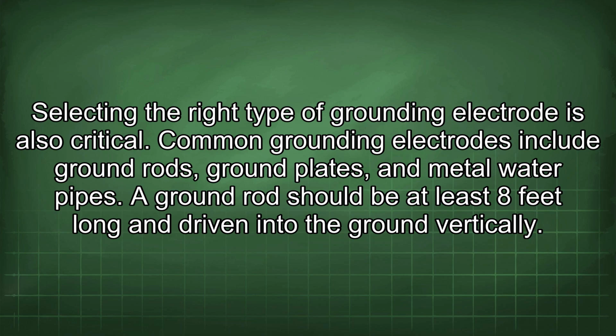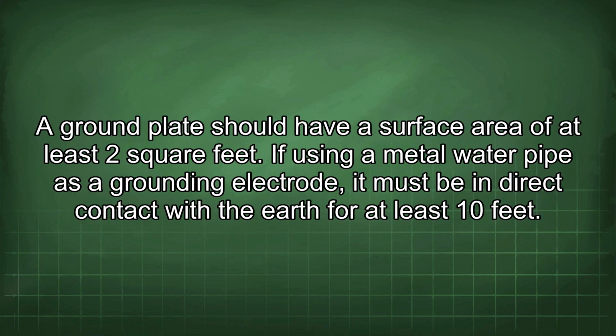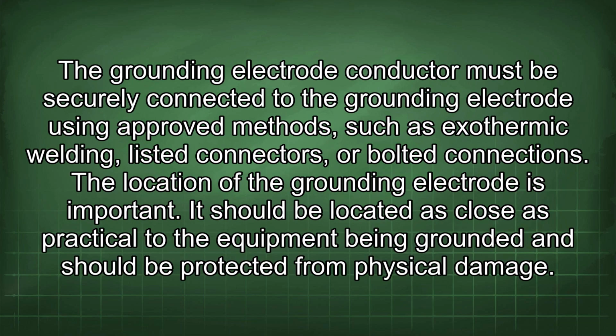Selecting the right type of grounding electrode is also critical. Common grounding electrodes include ground rods, ground plates, and metal water pipes. A ground rod should be at least 8 feet long and driven into the ground vertically. A ground plate should have a surface area of at least 2 square feet. If using a metal water pipe as a grounding electrode, it must be in direct contact with the earth for at least 10 feet. The grounding electrode conductor must be securely connected to the grounding electrode using approved methods such as exothermic welding, listed connectors, or bolted connections.